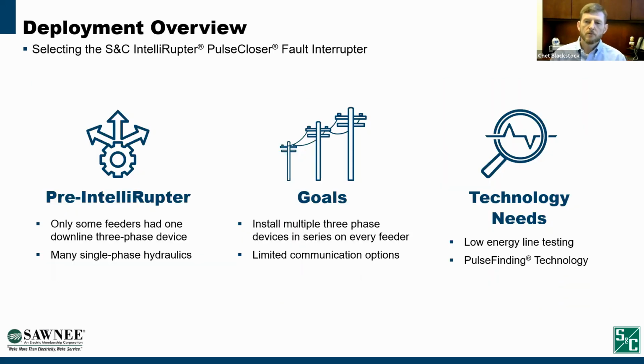Next slide. So before we started deploying IntelliRupter several years ago, our system was comprised of feeders. We only had a few feeders with downline three-phase reclosers. We had many, or still have, many single-phase hydraulic reclosers and some large fuses. And we were only able to squeeze one three-phase device between our circuit breaker and all of our downline devices and still maintain coordination. So when we decided to implement more three-phase devices, we wanted to install more devices in series on a single feeder and still maintain that segmentation. So we had to do this with limited communication as well, because we didn't have the communication technology at that time in order to do any kind of high-speed communication, enhanced coordination.